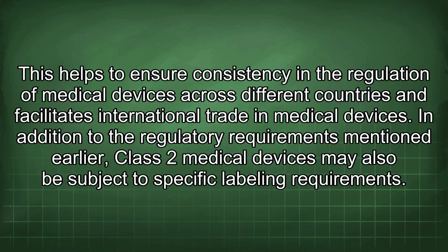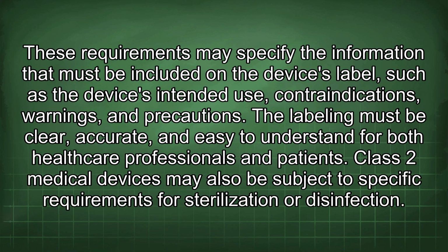In addition to the regulatory requirements mentioned earlier, Class II medical devices may also be subject to specific labeling requirements. These requirements may specify the information that must be included on the device's label, such as the device's intended use, contraindications, warnings, and precautions. The labeling must be clear, accurate, and easy to understand for both healthcare professionals and patients.